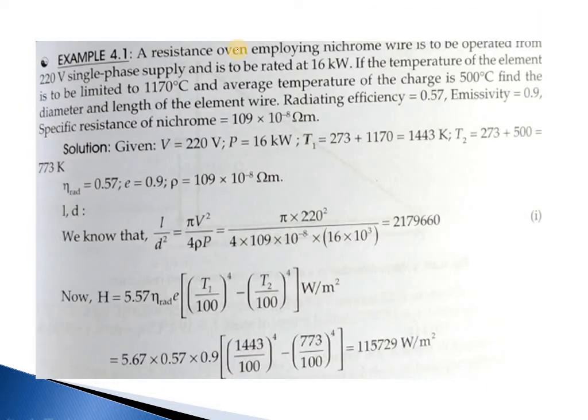Now let us take some examples related to electrical heating. Example 1. A resistance oven employing nichrome wire is to be operated from a 220 volt single phase supply and is to be rated at 16 kilowatts. The temperature of the element is to be limited to 1170 degrees centigrade and the average temperature of the charge is 500 degrees centigrade. Find the diameter and the length of the element wire. Radiating efficiency is 0.57, emissivity 0.9, and the specific resistance of nichrome is given as 109 into 10 to the minus 8 ohm meter.